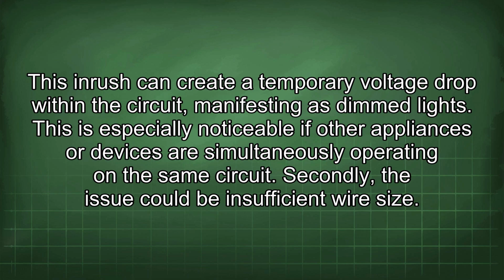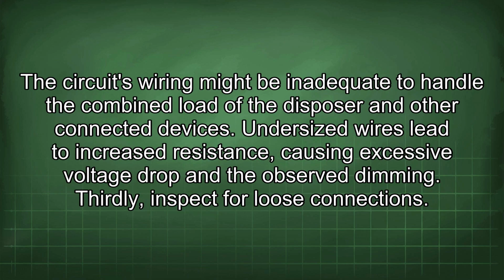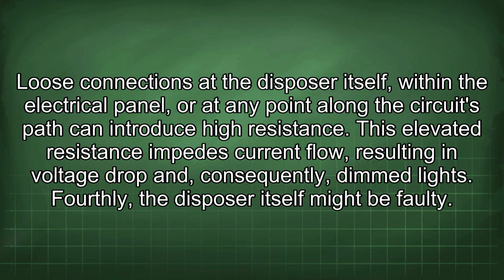Secondly, the issue could be insufficient wire size. The circuit's wiring might be inadequate to handle the combined load of the disposer and other connected devices. Undersized wires lead to increased resistance, causing excessive voltage drop and the observed dimming. Thirdly, inspect for loose connections. Loose connections at the disposer itself, within the electrical panel, or at any point along the circuit's path can introduce high resistance. This elevated resistance impedes current flow, resulting in voltage drop and, consequently, dimmed lights.